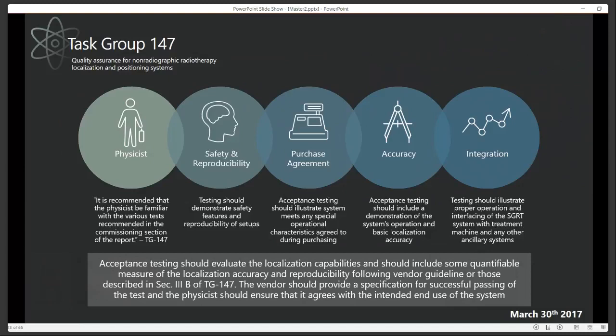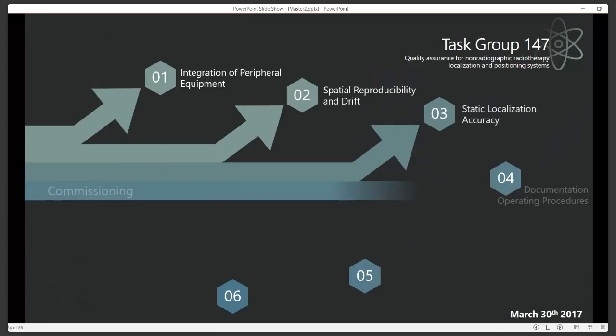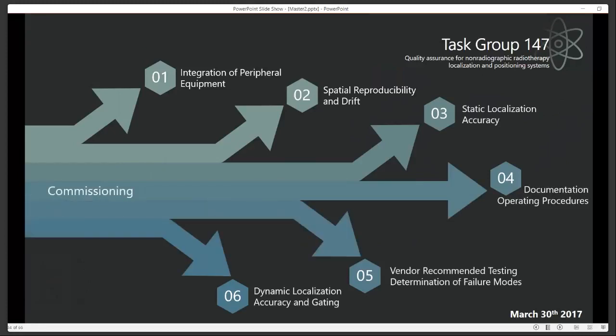The vendor should provide a specification for successful passing of these tests. The physicist should ensure that those agree with the intended use for the system. If you bought a system and the specification is 2 millimeters accuracy, don't plan on using that for SRS, whether you agreed to it after the fact or not. Once you purchased it, if you agreed to 2 millimeters, you're going to have 2 millimeters, and that's not an SRS system. Commissioning is then laid out separately in the report.